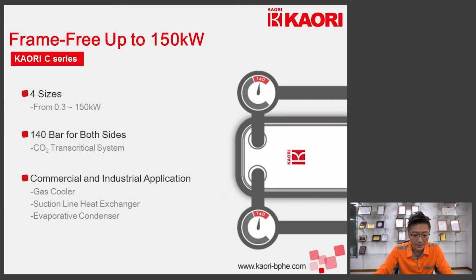One of the main advantages of Kaori's CO2 brazed plate heat exchanger is its frame-free design, so there is no extra reinforcement frame around the heat exchanger. It also offers a wide range of capacities from 0.3 to 150 kilowatts, and it can be made with 140 bar on both sides, making it a good choice for CO2 transcritical systems. As for commercial and industrial applications, it can be used in gas coolers, suction line heat exchangers, and evaporative condensers.